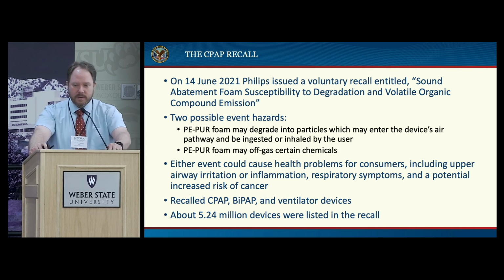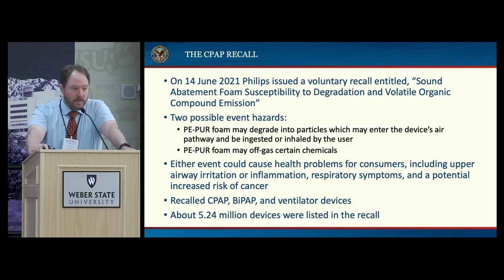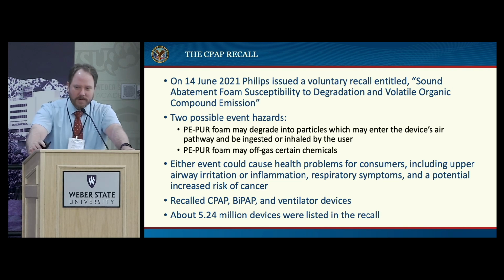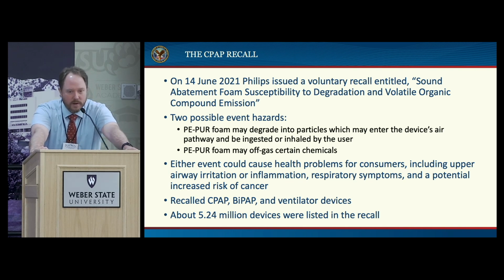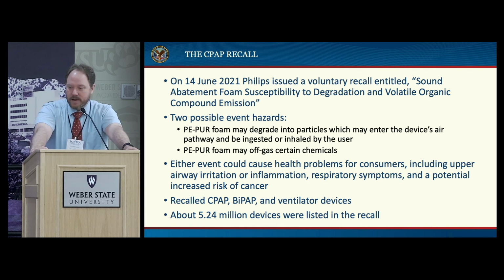But the main issue with the mask recall was revealed on the 14th of June in 2021, though our representative told us in April what was happening and the writing on the wall. He isn't the rep anymore, but I think he saw what was going to happen. But there's a foam in the machine that's used to reduce sound. It's sitting in the air channel. Sound and vibration is the goal, to reduce that for the patient's comfort. And there were reports that this foam was susceptible to degradation and off-gassing of certain volatile organic compounds, with 2 possible event hazards. First, this polyester polyurethane foam may degrade into particles which may enter the device's air pathway and be ingested or inhaled by the patient. And then, it may also off-gas certain chemicals. Either event could cause health problems for the consumer, including upper airway irritation.